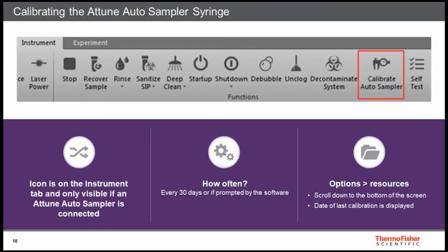To calibrate the Attune NxT and the Autosampler, run the startup script, and upon completion of startup, calibrate the Autosampler by clicking on the Calibrate Autosampler icon located in the instrument ribbon, also shown here. The process should take about a minute for the Attune Autosampler to calibrate. In case of any issues, please contact Thermo Fisher Scientific Support.